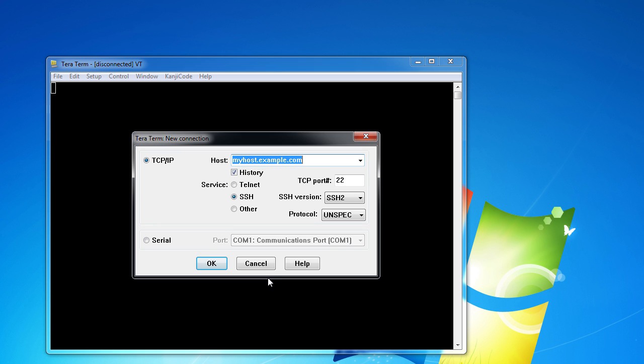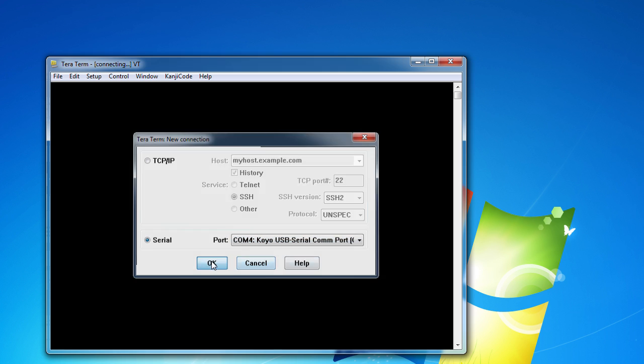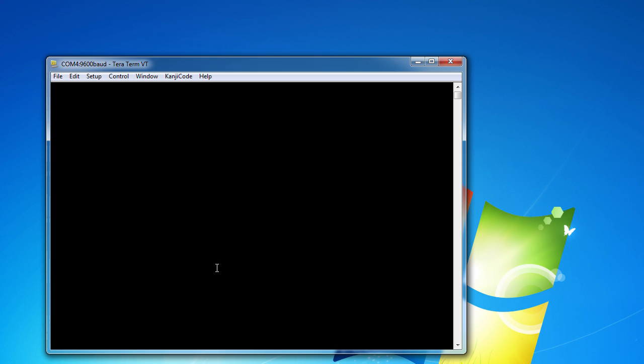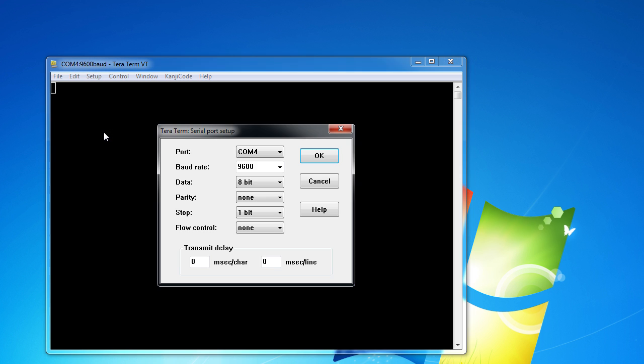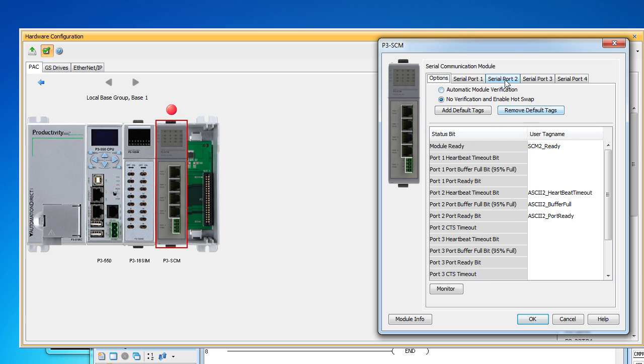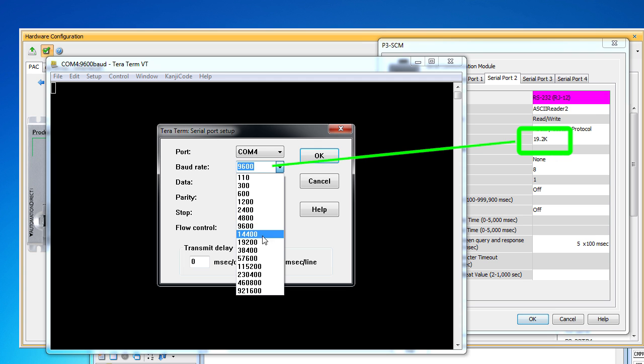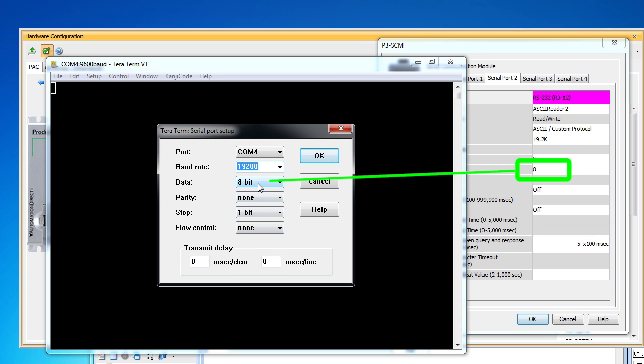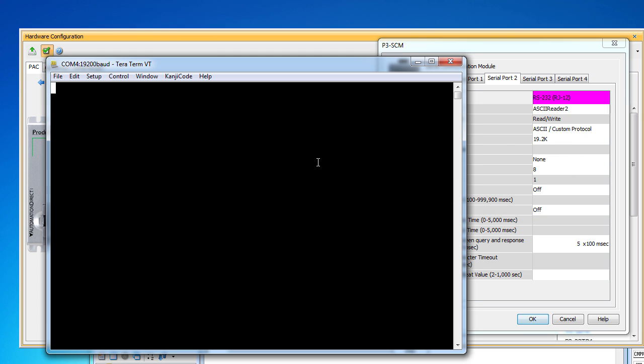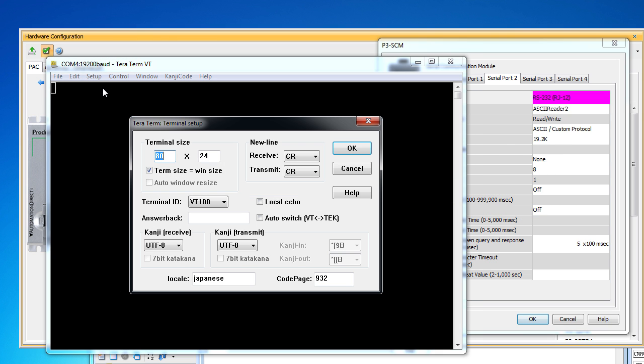When I bring up that terminal program, I just tell it I want to do serial on the port that the converter is connected to. I want to set up the serial port on the PC to match the serial port we just set up on the Productivity 3000. Here is the dialog from the Productivity 3000. And we see that we need 19.2 kbaud, 8 bits, no parity, one stop bit and no flow control. Perfect. I am going to tell the terminal to echo the characters so I can see what I am typing and make sure it sends a return at the end of each line since that's what we told the ASCII IN instruction to expect.